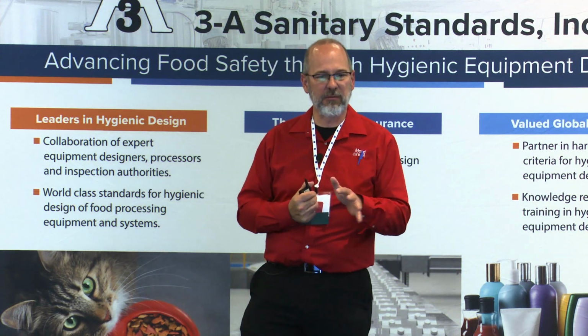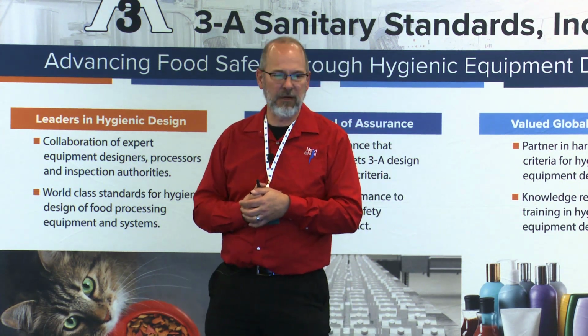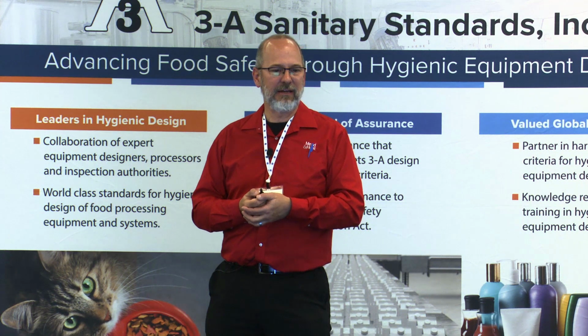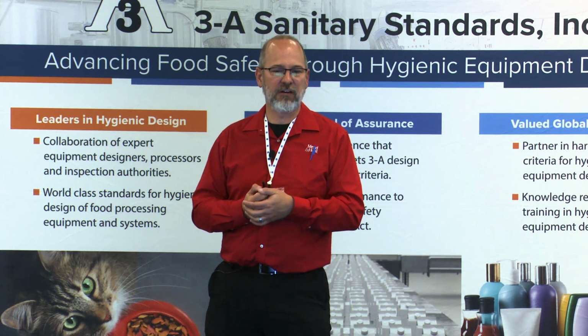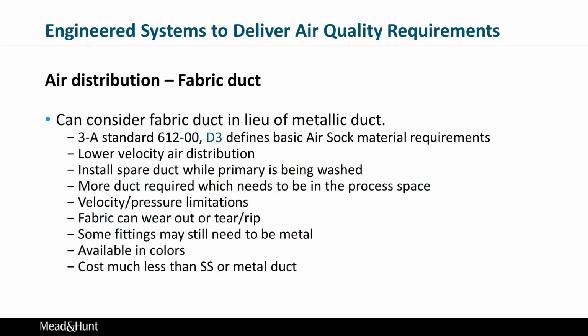Another thing we're starting to see a little bit more of is fabric duct in more and more facilities. The 3A standard does address fabric duct as well, so I won't go into it. Some things to note about fabric ductwork. The ductwork's a little bigger because you have to go at lower velocities. High velocities will tear and rip the fabric, so typically you don't see it at real high velocities.